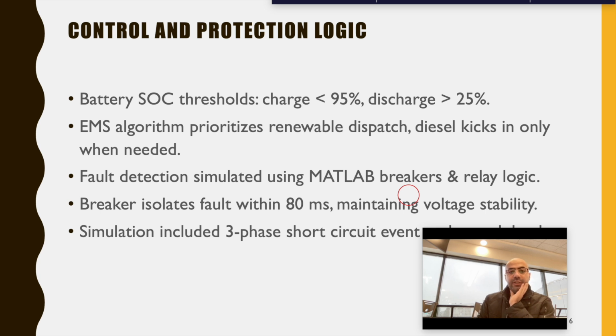Here we have control and protection logic. Regarding battery state of charge thresholds, battery charging is limited below 95% and battery discharge stops below 25%. Regarding dispatch logic, the energy management system chooses renewable energy first, and diesel is only used when solar and battery are insufficient. Regarding fault simulation, we used MATLAB to simulate a three-phase short circuit, and a breaker isolates the fault in just 80 milliseconds, preserving system voltage. These controls protect both the equipment and ensure uninterrupted power delivery.